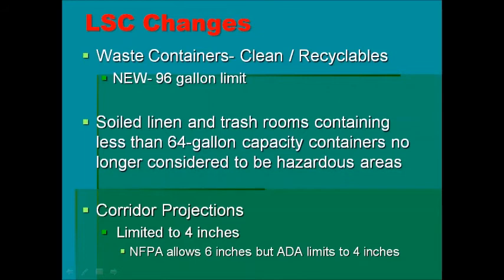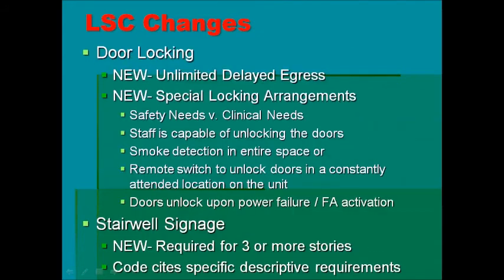So CMS is saying 4. And then there are some states that have other agencies, like California, that has an organization known as OSHPD. And if you're on the line from California, you're shaking your head right now, there are even more stringent requirements. So you need to be aware of corridor projection requirements as well. There are some new requirements when it comes to door locks and locking arrangements. And without getting too much in detail on this, because I could spend a full hour talking on locking arrangements, you need to understand that there are some relief elements to the new code.